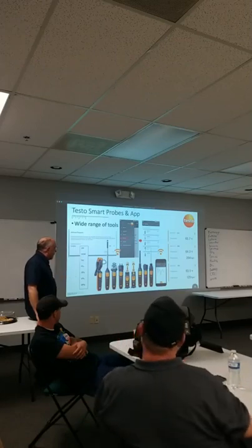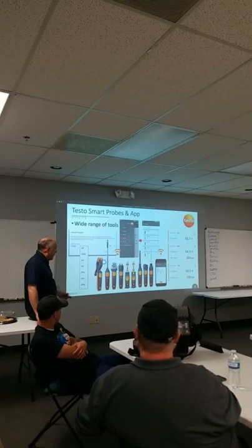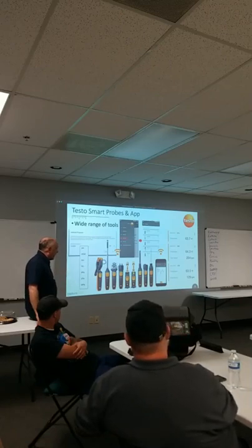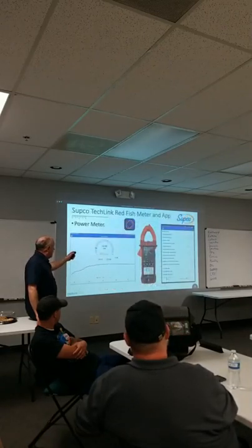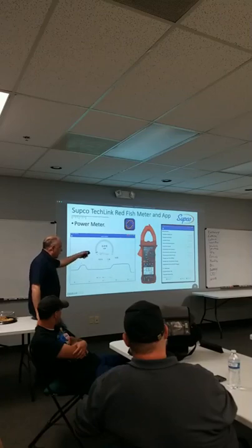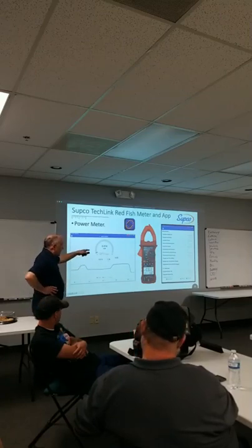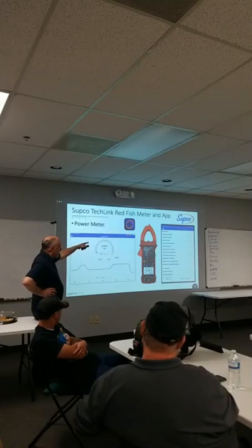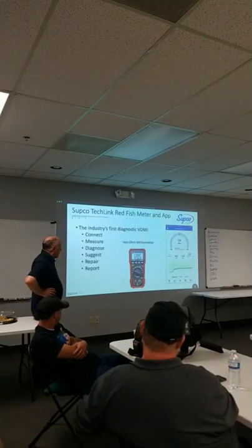Testo's probably got the most exclusive line of stuff. It's got a very clunky German application, but they do make some of the best measurements in the industry. They've got really high-end quality probes. Redfish meter, we've got that tied in. It was the first meter that would do some analysis of some of the components, and it allowed us to bring it into the application and do voltage drop tests, service and utilization voltage tests, test components like thermocouples, flame rods, start capacitors, run capacitors, that kind of stuff. It was really the industry's first diagnostic meter.